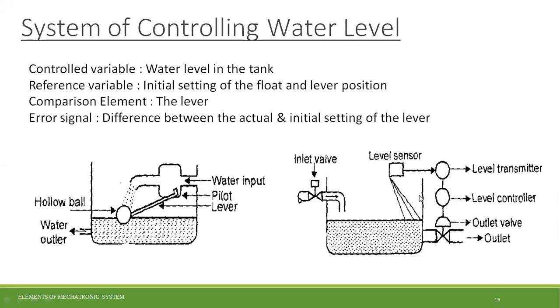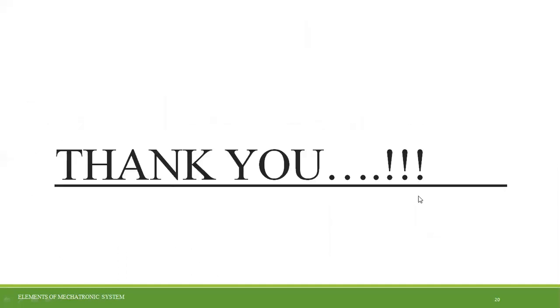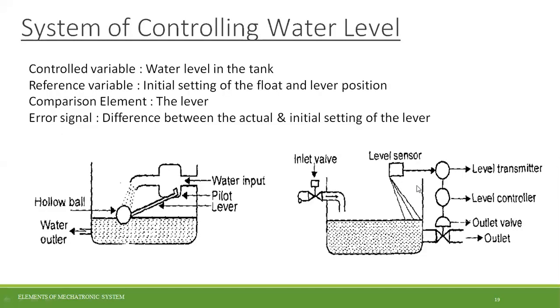up to the maximum level it has to be filled. After reaching the maximum level of the water tank, the level sensor identifies that the maximum level has been achieved, and transmits that signal using the level transmitter, and the level controller gives the signal to switch off the motor's electrical power supply. So there is no involvement of human beings here.